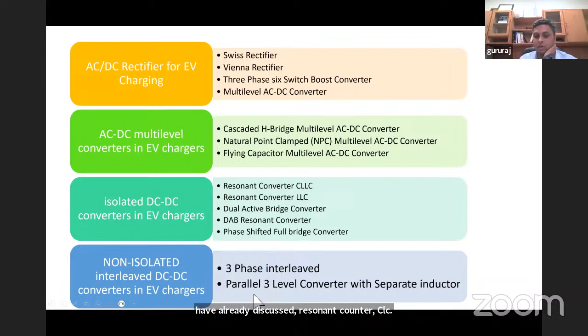The first one is the three-phase buck-type rectifier. The key requirements from the grid operator for an EV charging station, whatever topology you adopt, generally include achieving power factor correction, with power factor as close as possible to unity, along with low THD, high efficiency, and high power density.